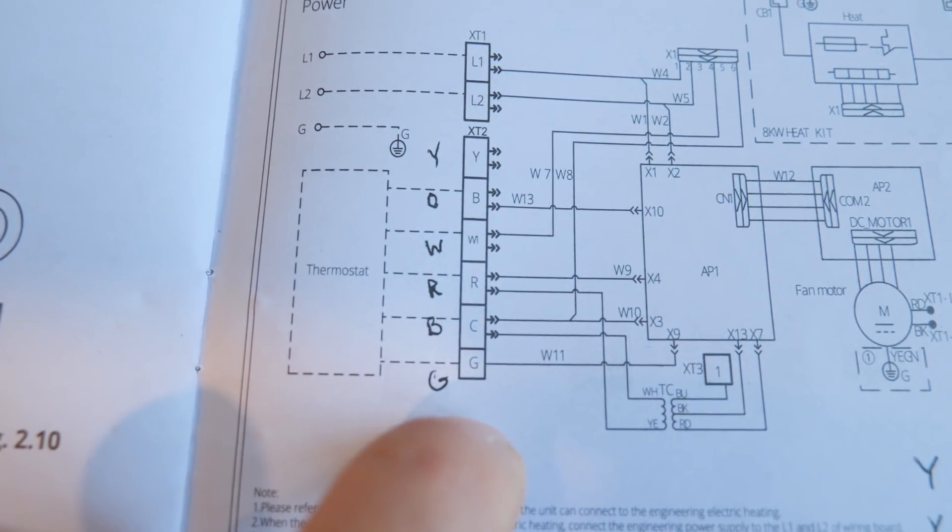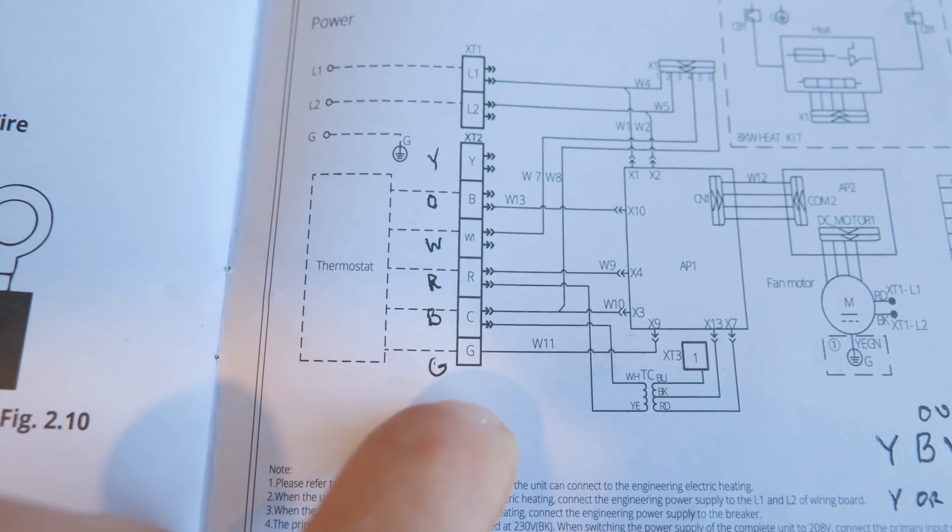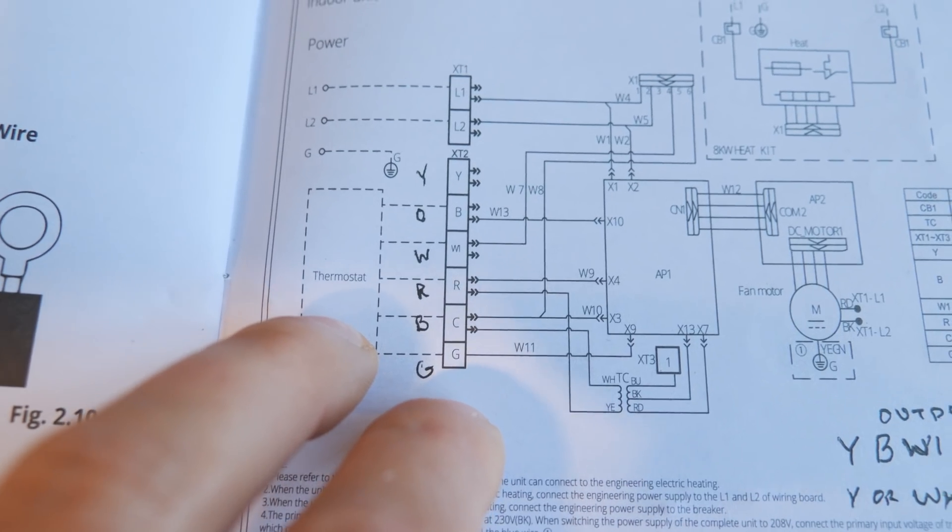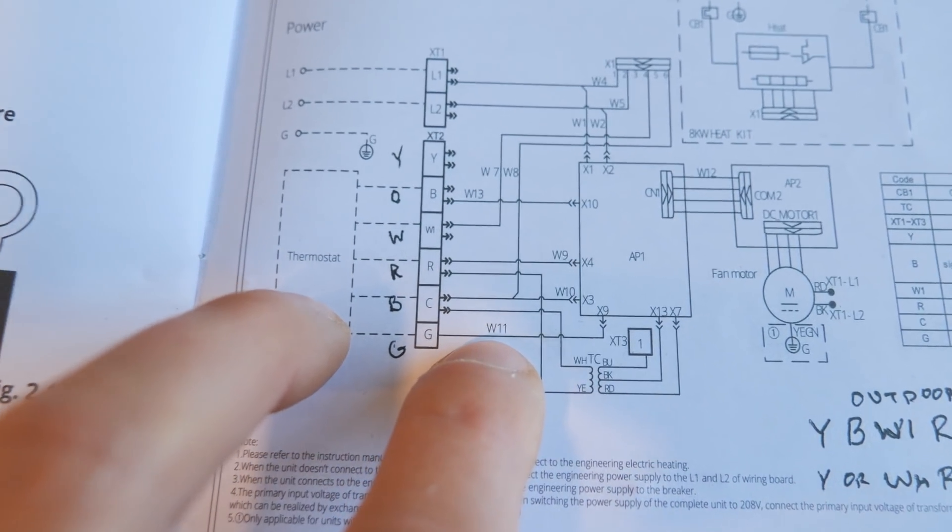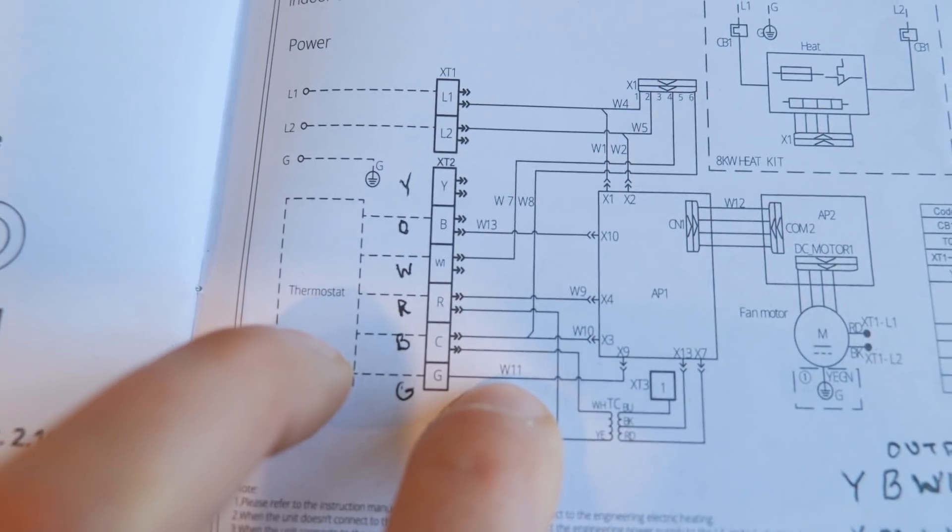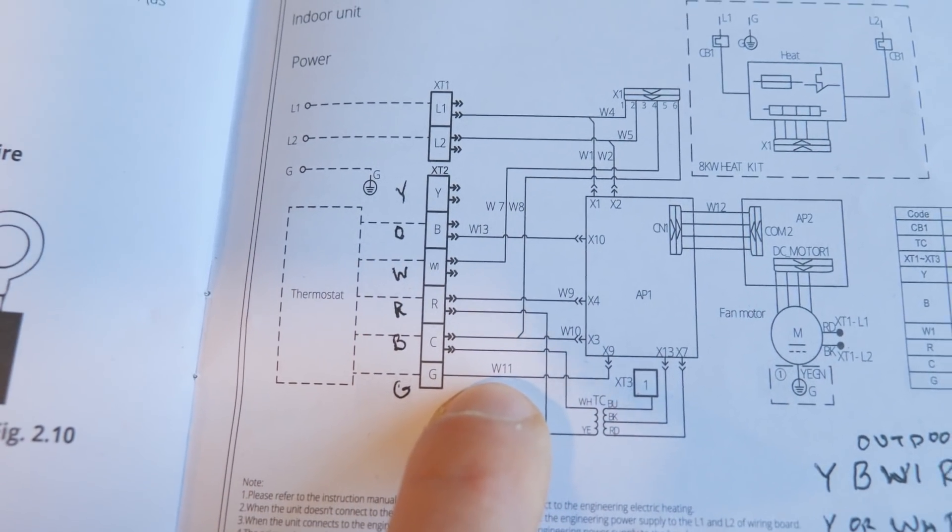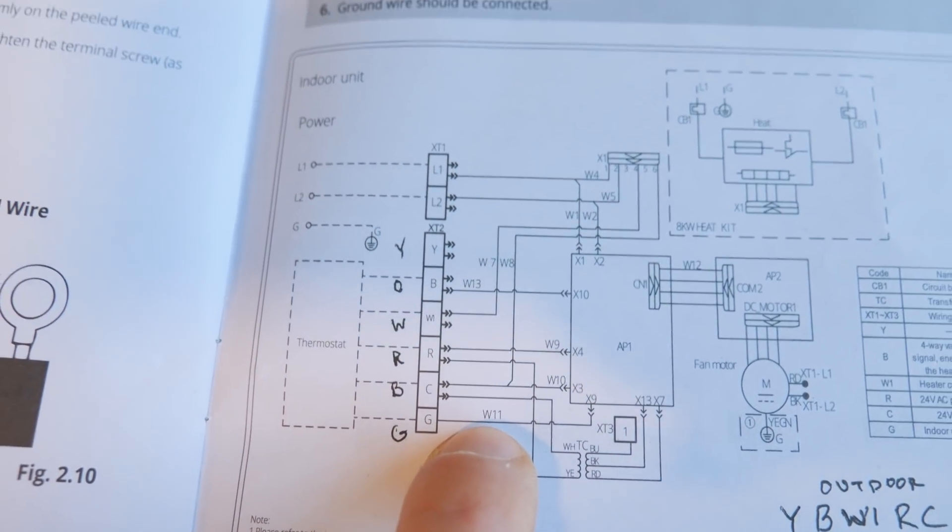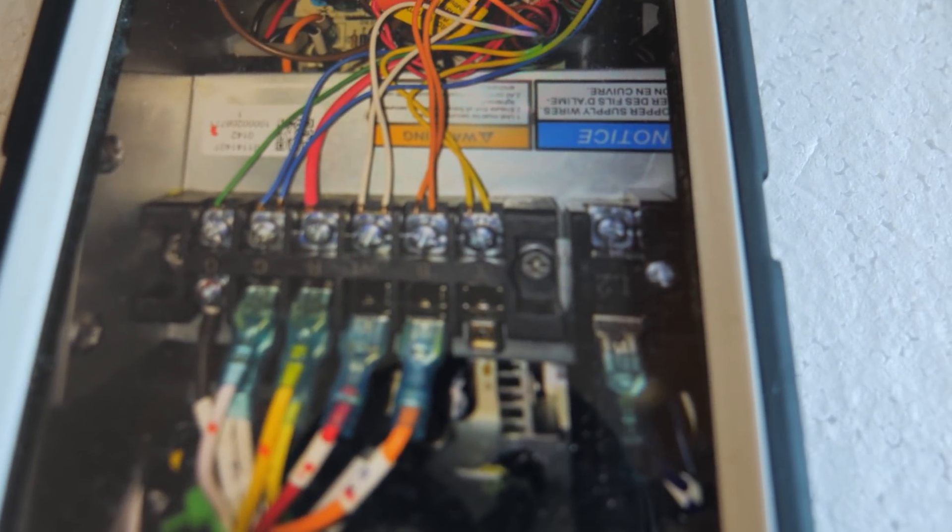On the indoor unit, this is the Mr. Cool Universal wiring. Yours will be different. So the thermostat wire to the indoor unit terminal, this is the wiring diagram. Now, what I did was take a picture of the actual wiring terminal on both the outdoor unit and the indoor unit.